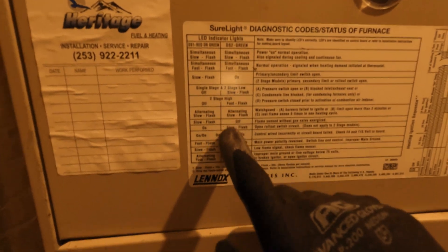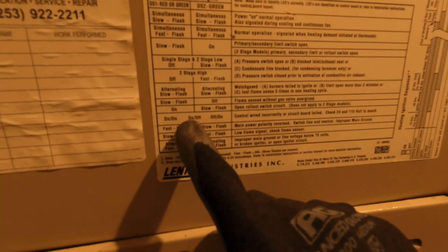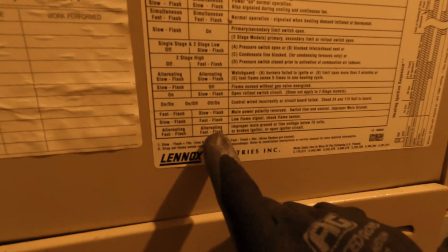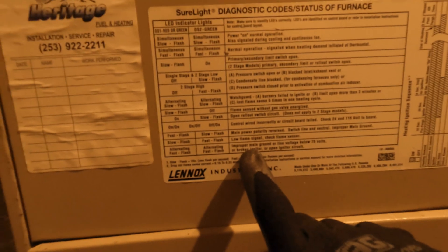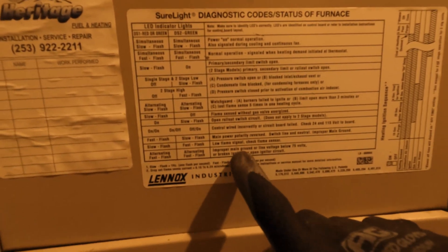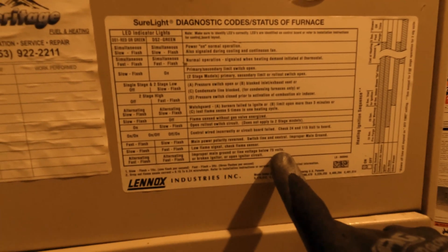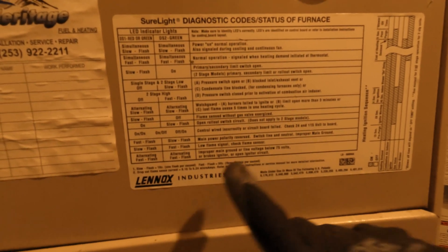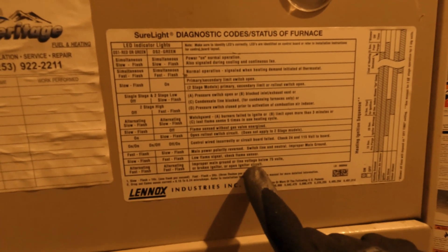It's showing red and green fast alternating flash right here. According to the chart, that means improper main ground, or line voltage below 75 volts, or a broken igniter, or an open igniter circuit.